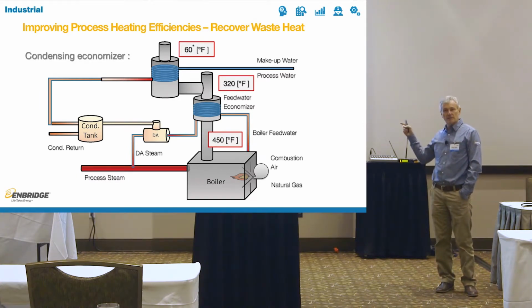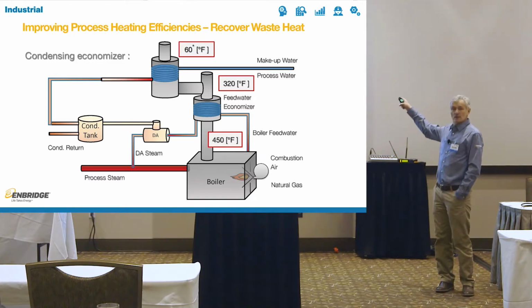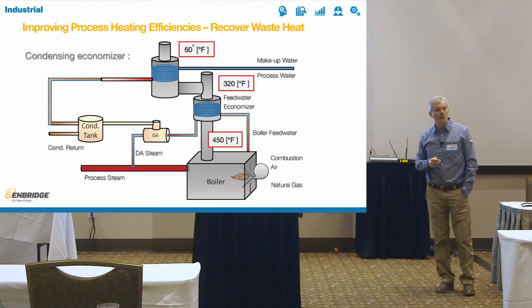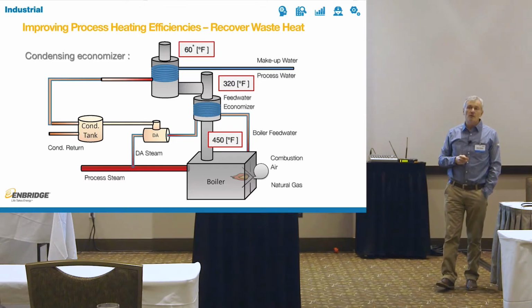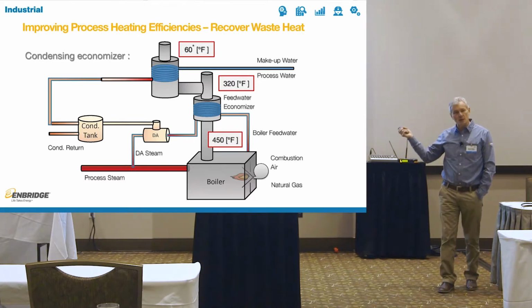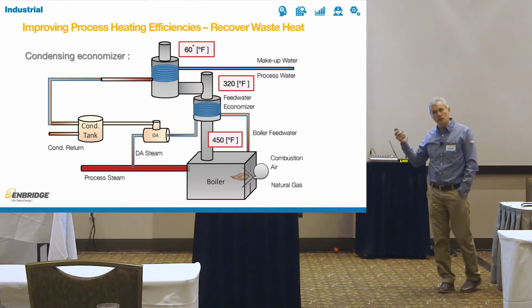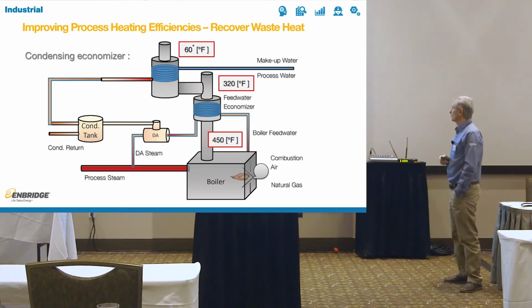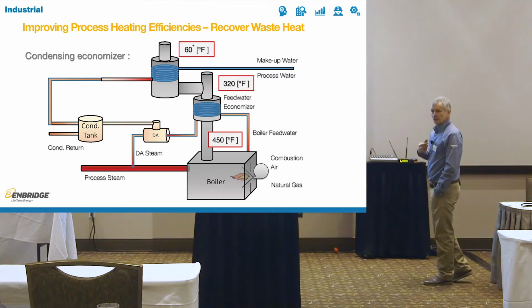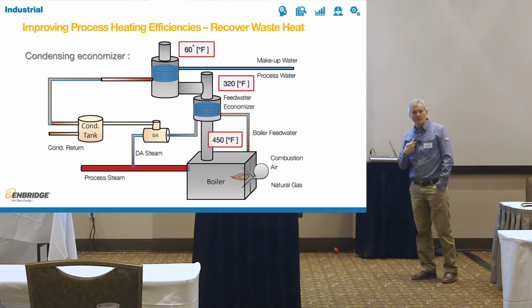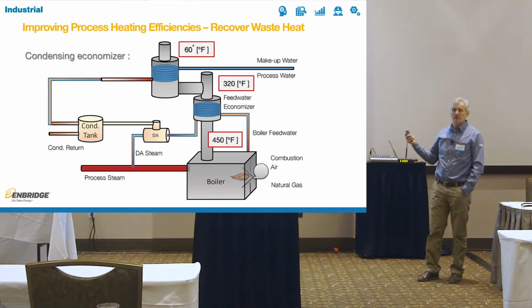I can get it from 50 degree F city water to 170, 180 degrees F water on the other side, for essentially waste heat out of the stuff that I'm already paying for. So it's not a net new source of energy. That's the benefit to me of the condensing economizers. And when I had the best examples of implementations, that's how I implemented condensing economizer.